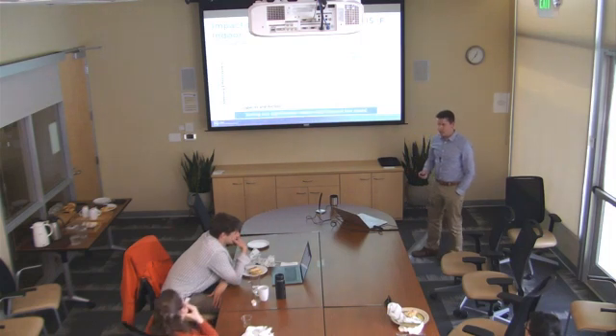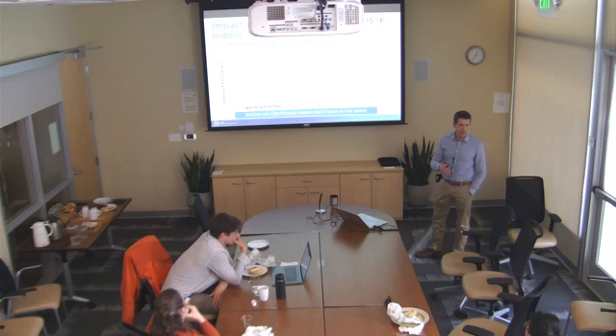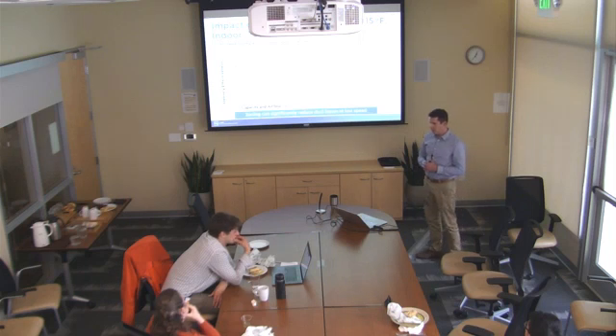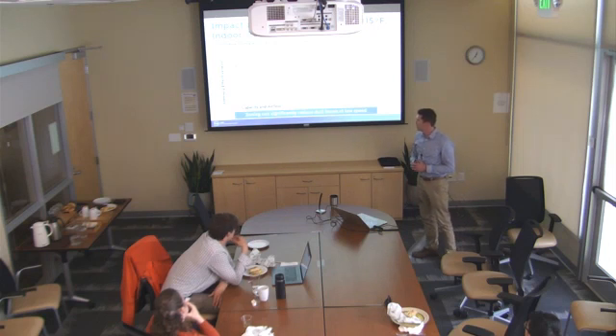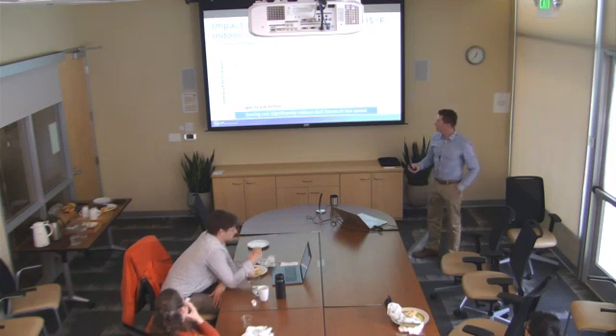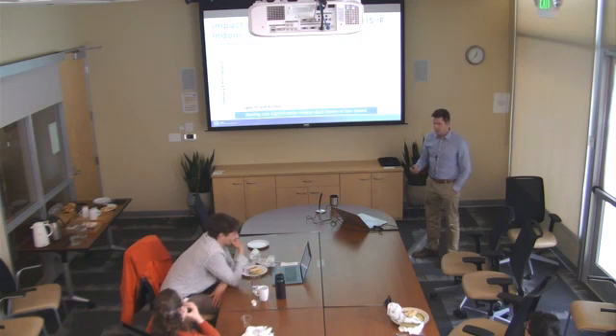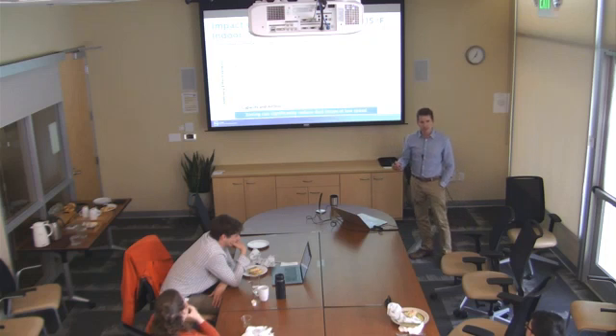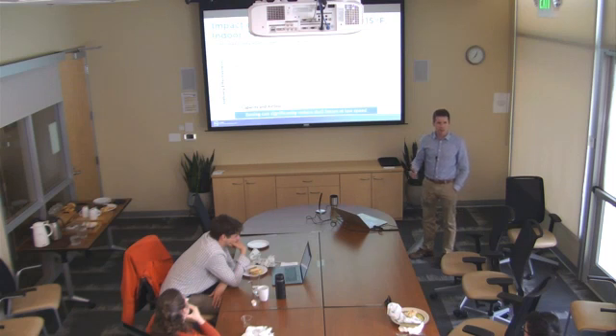So next we added zoning equipment. Again, zoning on the air side in the attic, so you're able to deliver this capacity to different parts of the house, not delivering it to the entire house at once. We can significantly improve performance. What you can see is the red line shows the delivery effectiveness of the duct system with zoning versus blue without at that hot condition. So you see, again, we're going down to 40% delivery effectiveness for the system without zoning, but we're able to maintain delivery effectiveness across all speeds of the equipment by including some kind of zoning equipment on the duct side.